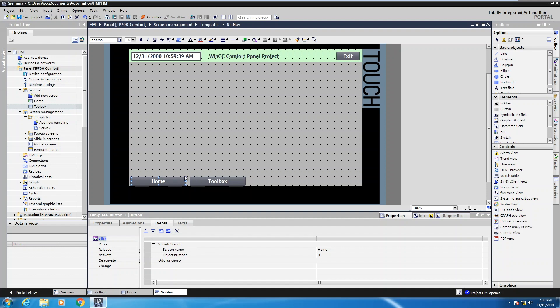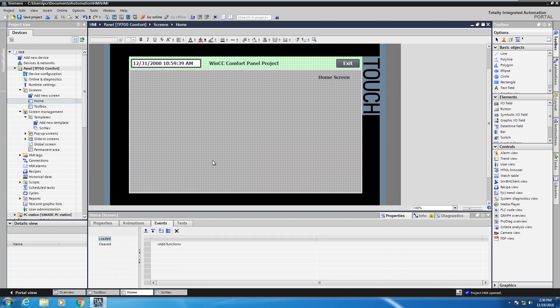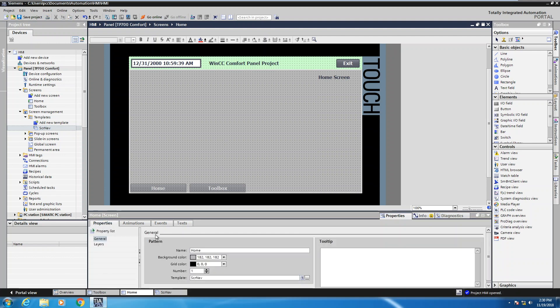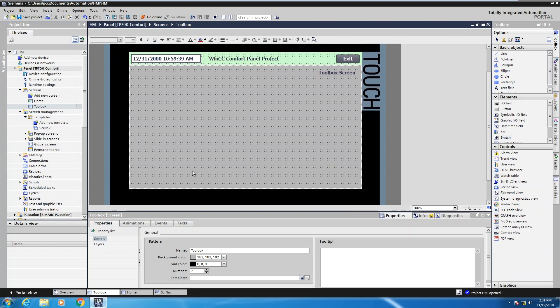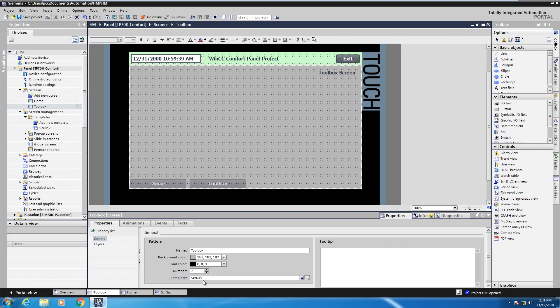Once these objects are on the screen navigation template I can open up the home screen. Looking at the home screen you'll notice there are no template objects on it. I can take the screen navigation template, drag it into the background, and in the properties for the home screen I assign screen nav to it. Now when the home screen is visible, the home and toolbox buttons show up translucent, indicating they reside on the template screen. Going to the toolbox screen, there are no navigation buttons there yet. I can come down to the template area, select the browse button, and browse for the screen navigation template. As soon as I assign it, those buttons show up translucent on this screen as well.